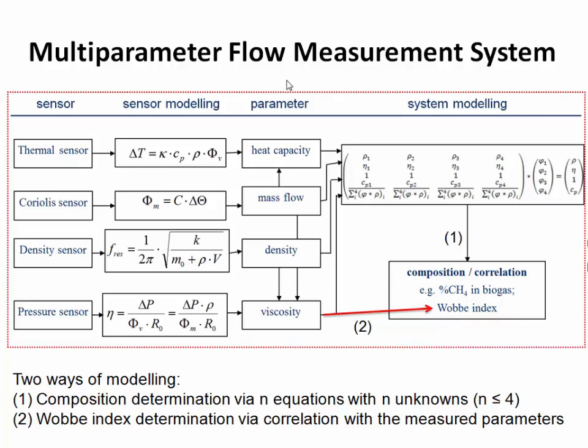So why is it necessary to measure more than one parameter? Because there are also systems existing which determine the Wobbe index only from the viscosity. Okay, that's interesting, and you could do that. However, for instance, if you have a gas mixture with not only methane, but also nitrogen gas and carbon dioxide, both nitrogen and carbon dioxide do not contribute to the Wobbe index. However, they will effectively have a different viscosity. So if you only measure the viscosity and try to derive the Wobbe index from that, and you have a mixture that also contains nitrogen and carbon dioxide, you have these bands of uncertainty, the top one and the bottom one.